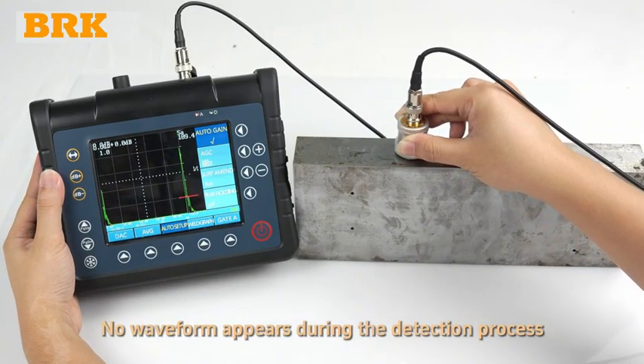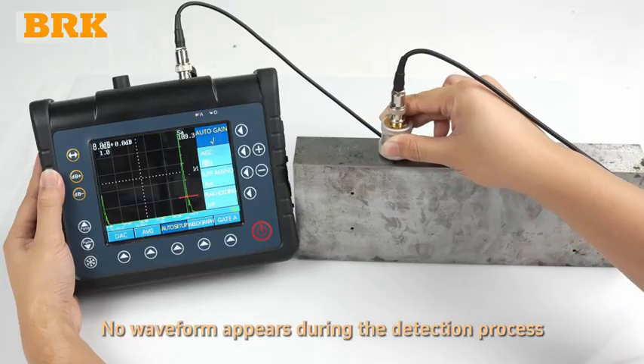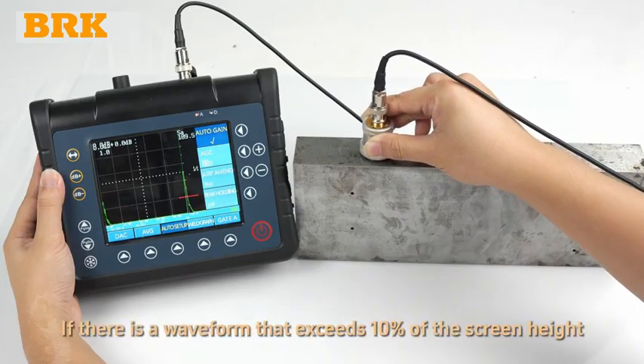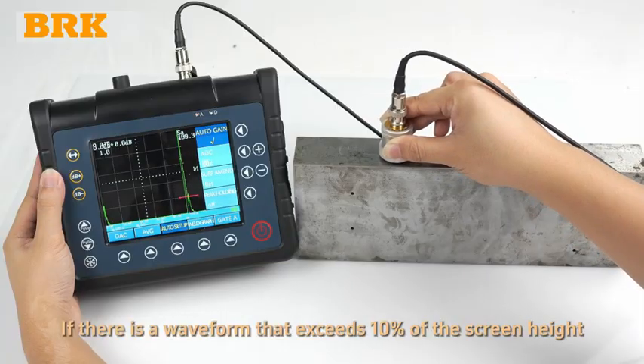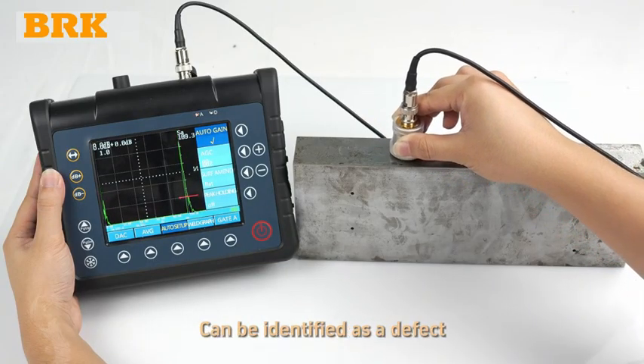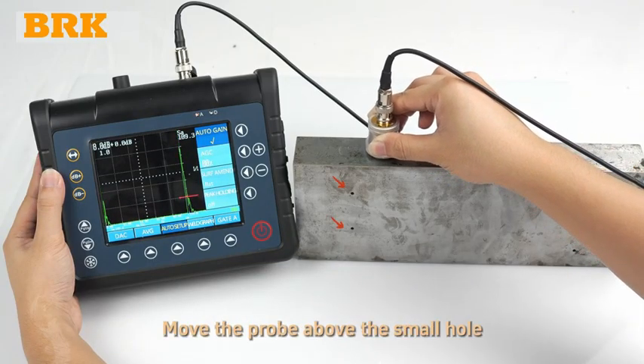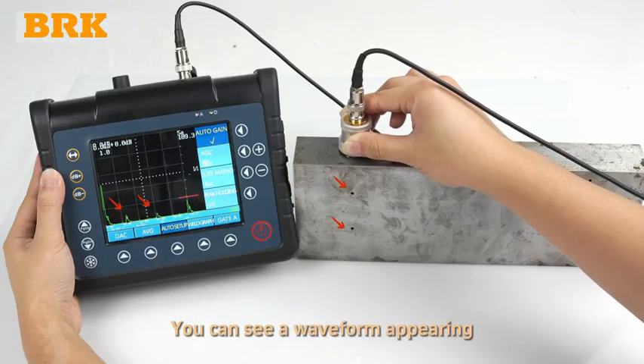No waveform appears during the detection process, indicating no defects. If there is a waveform that exceeds 10% of the screen height, it can be identified as a defect. Move the probe above the small hole. You can see a waveform appearing.